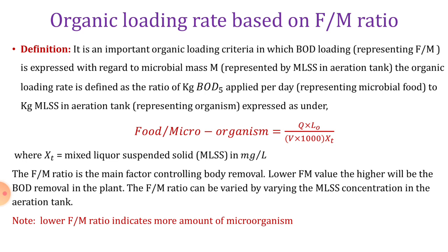The organic loading rate is defined as the ratio of kg BOD5 applied per day, which represents the microbial food, to kg MLSS in the aeration tank, representing the organisms, expressed as under. Food to microorganism will be given as Q into L0 divided by, in brackets, V into 1000 into XT, where XT is the mixed liquor suspended solids.